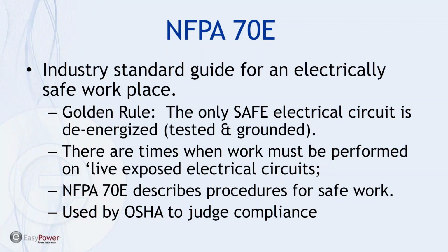So NFPA 70E is a document that's referred to pretty much by all as the industry standard guide for an electrically safe workplace. And the golden rule, according to NFPA 70E, is the only safe electrical circuit is a de-energized circuit which has been tested and grounded if possible. Well, there are times when work must be performed on live exposed electrical circuits, and NFPA 70E describes the procedures for safely working and the conditions which permits that. It's also the document that's referred to or used by OSHA to judge compliance when a company has a problem. And so that's what we're going to be referring to as we get into a discussion of arc flash.